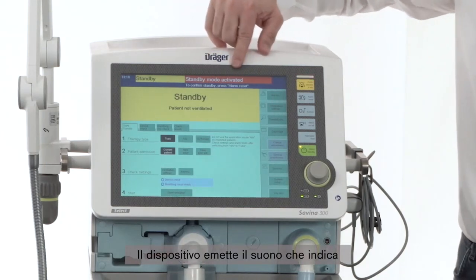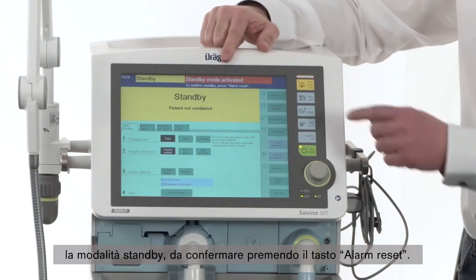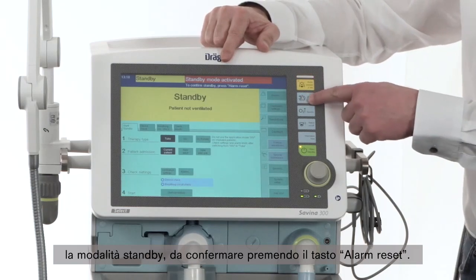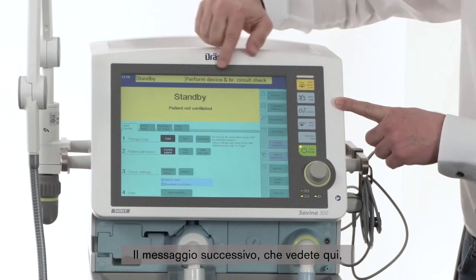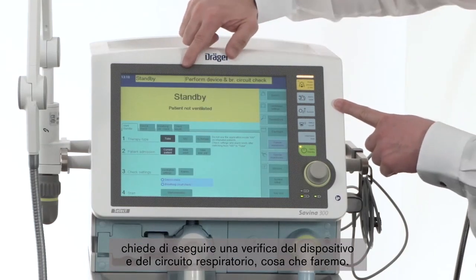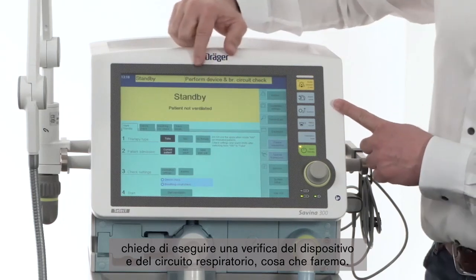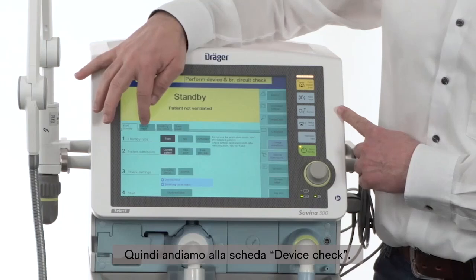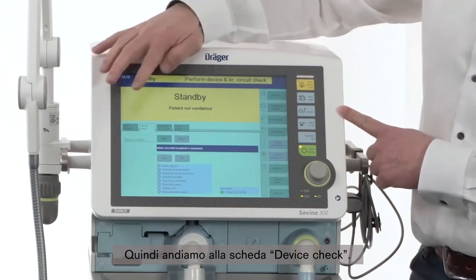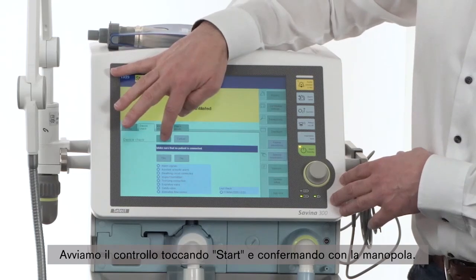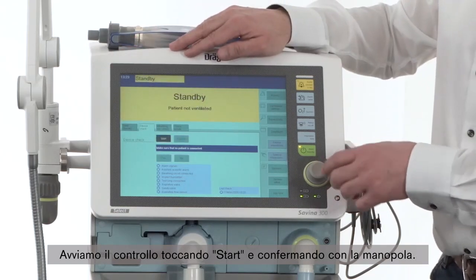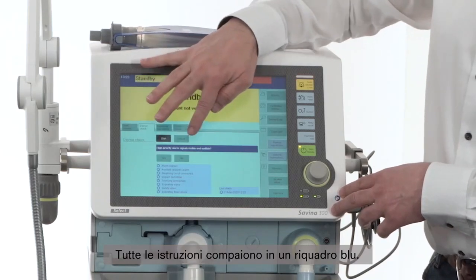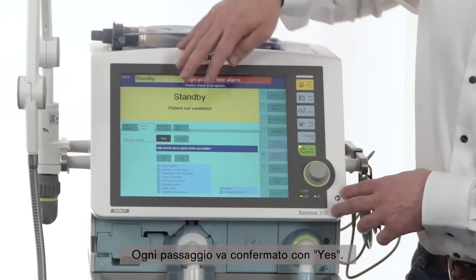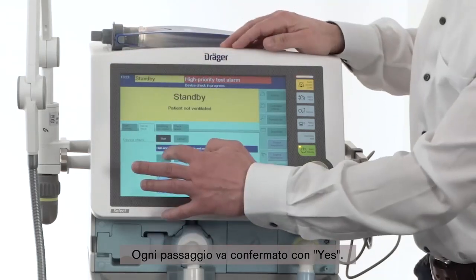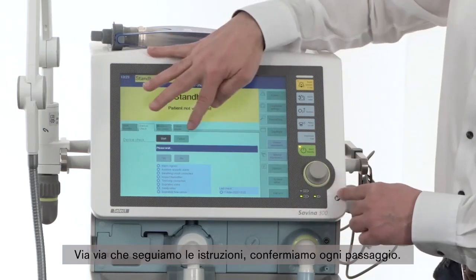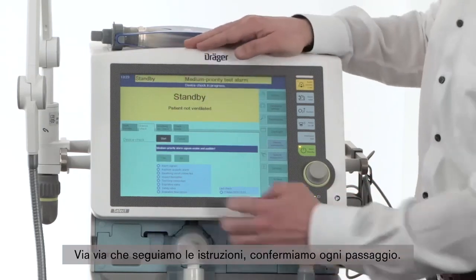The device will alarm standby mode. The standby mode has to be confirmed with the knob alarm reset. The next message, which you can see here, is to perform a device and a breathing circuit check, which we will do now. In the first step, please go to the tab Device Check. Please start the device check by tapping Start and confirm with the rotary knob. Every instruction you can read in the blue field, and please confirm each step with Yes. We are following the instructions and every single step will be confirmed.